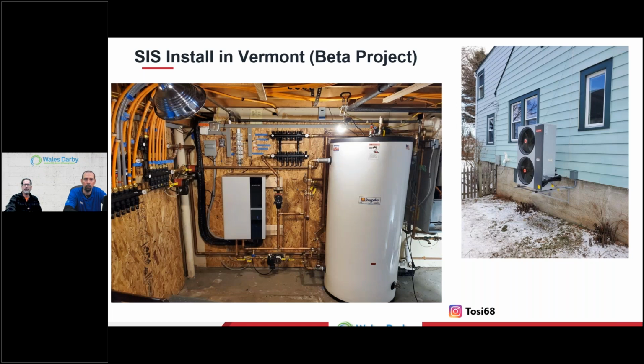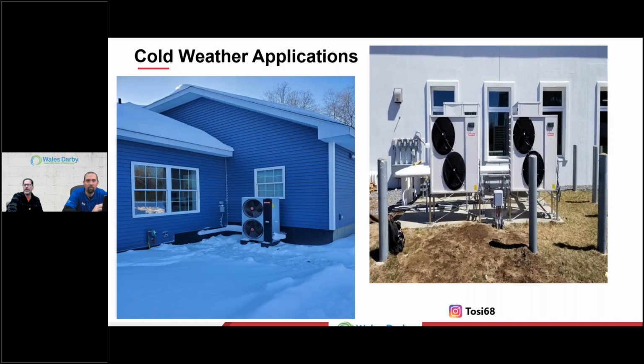Here's some other photos, indoor and outdoor, getting it off the ground. Again, free air is everything for anything that needs airflow across a coil. Defrost, drainage, icing, good storage here in that other picture. And then obviously we're doing low temperature again. So if you have applications where low temperature is an option, it can take in and consider some other source besides maybe a wall-mounted boiler. Cold climates we're not afraid of. Again, envelope over equipment. What is the load? Let's figure that out first, and then we marry it with emitters that allow low water temperature to achieve comfort.